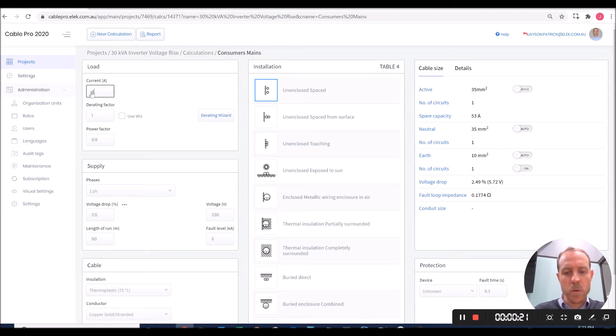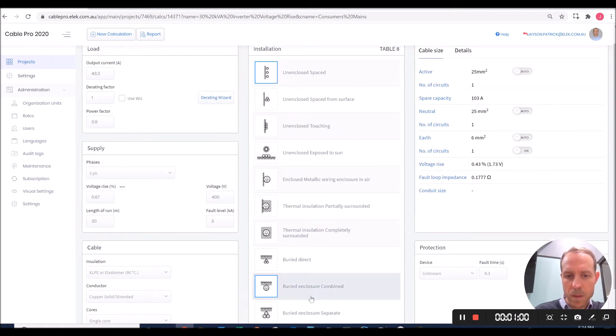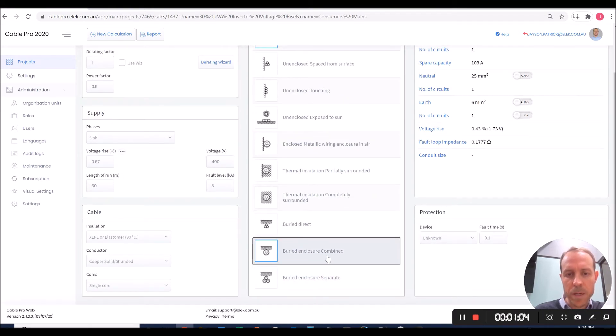The load current was 43.3 amps. I'm going to change voltage drop to voltage rise. It's a three-phase inverter. For the consumer's mains, the voltage rise should not exceed 0.67%. The length of the run is 30 meters. 400 volt system. We're going to use XLP insulated cables, single cores, copper conductors. The installation is going to be buried in a combined enclosure.